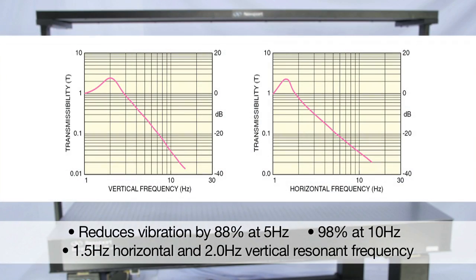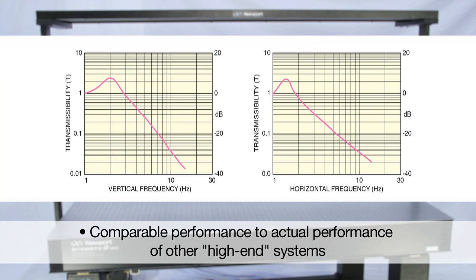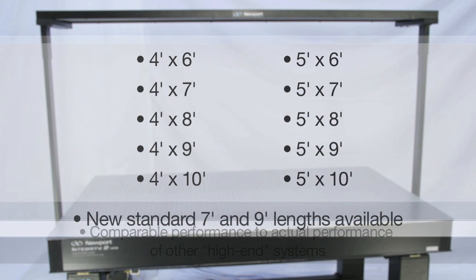The Integrity VCS isolated support platform includes active leveling pneumatic isolators that attenuate transmitted floor vibrations by 88 percent at 5 hertz, 98 percent at 10 hertz, and have a 1.5 hertz resonant frequency so that even the most sensitive experiments are not disturbed by building vibrations. This level of performance is comparable to the actual performance of many other high-end systems offered by other manufacturers.